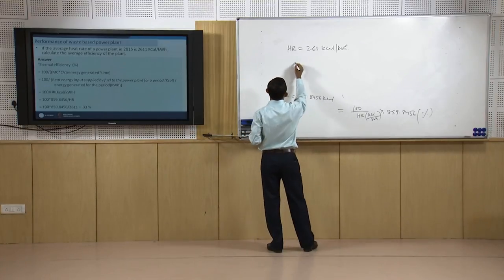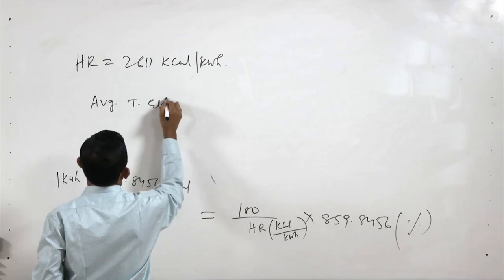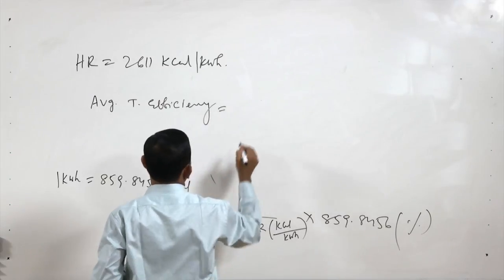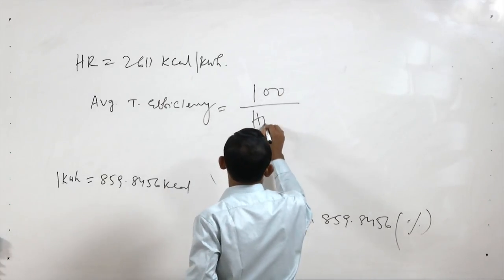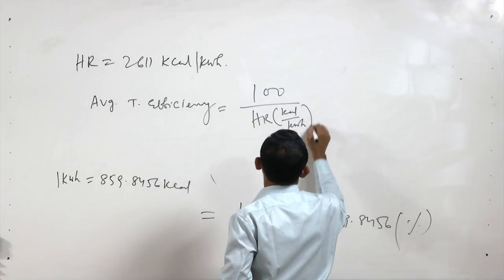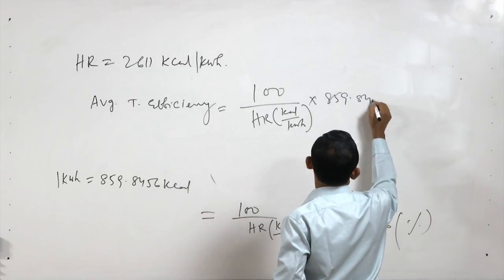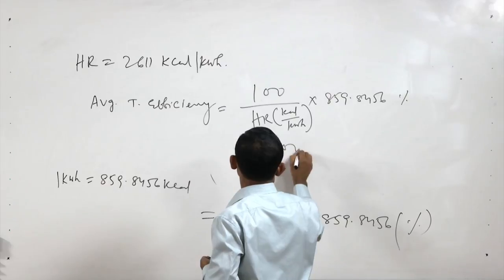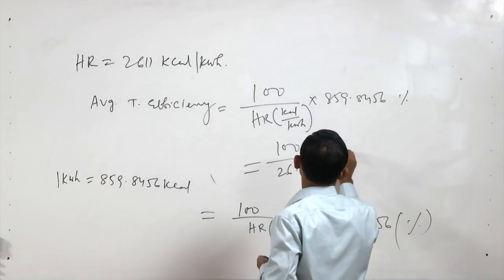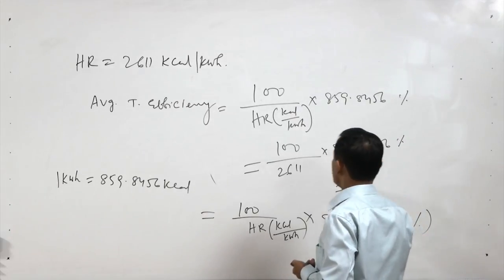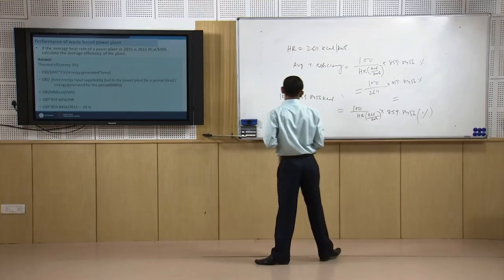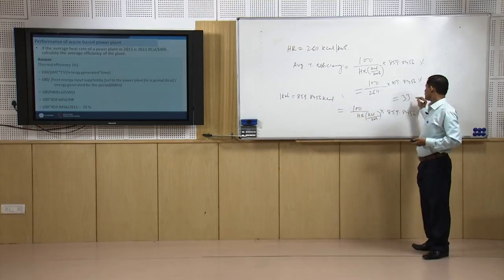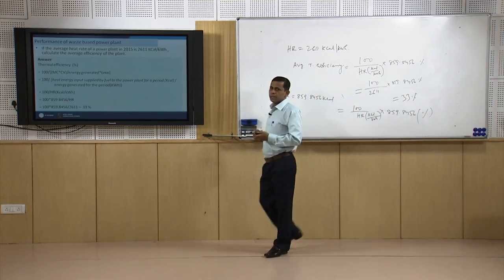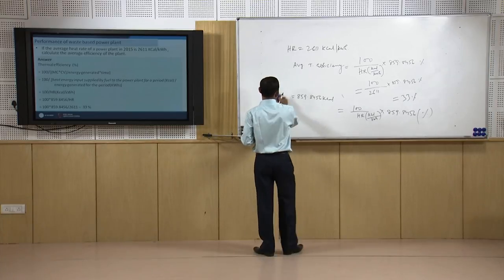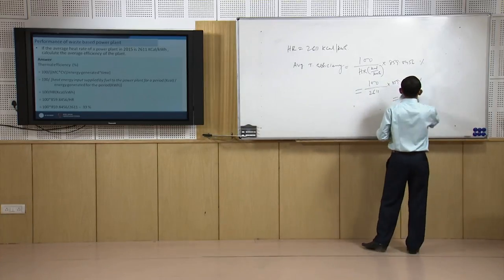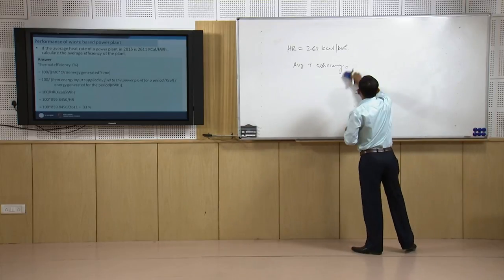Average thermal efficiency is equal to 100 divided by HR in kilocalorie per kilowatt hour, into 859.8456, in percentage. So in this case, 100 divided by 2611 into 859.8456 percentage, that is equal to around 33%. So that is equal to 33%. Now we have seen how to calculate the thermal efficiency on the basis of heat rate and the energy supplied, and how much energy we are getting from the thermal power plant.